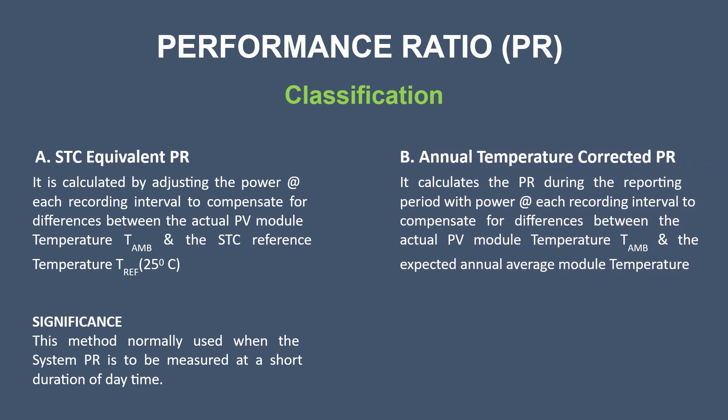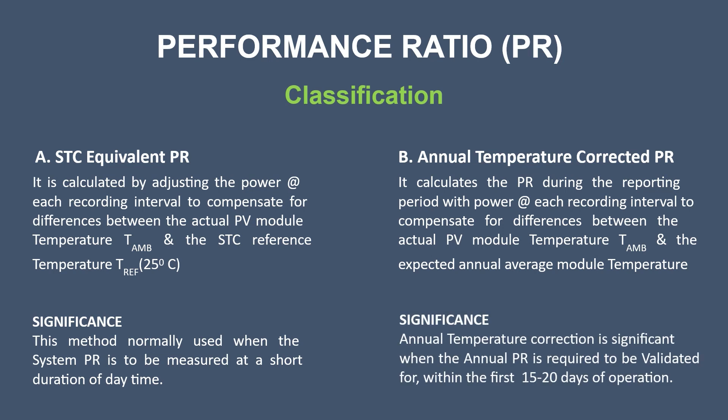Annual temperature corrected PR is similar to the previous one. Here, PR is calculated by adjusting the reporting period with respect to power to compensate for the difference between the actual PV module temperature and the expected annual average module temperature. This annual temperature correction is very significant when the annual PR is required to be validated within the first 15 to 20 days of operation.